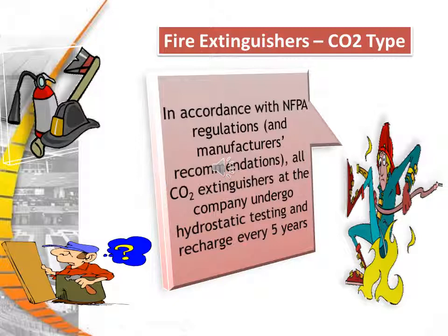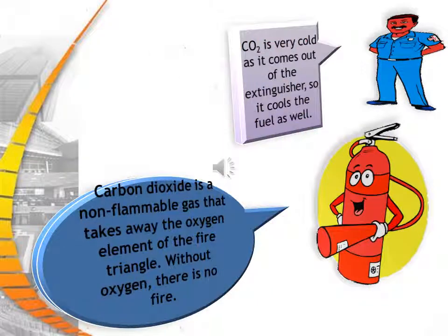CO2 continued. According to NFPA regulations and manufacturer recommendations, all CO2 extinguishers at a company undergo hydrostatic testing and recharging every 5 years. CO2 is very cold when it comes out of the extinguisher, so it cools the fuel as well. Carbon dioxide, however, is a non-flammable gas that takes away the oxygen element of the fire triangle. Without oxygen, there is no fire.